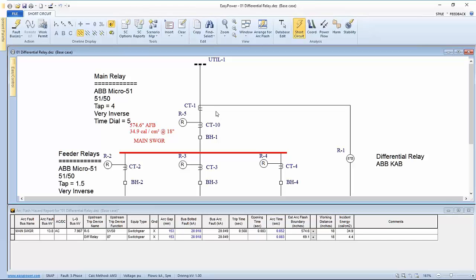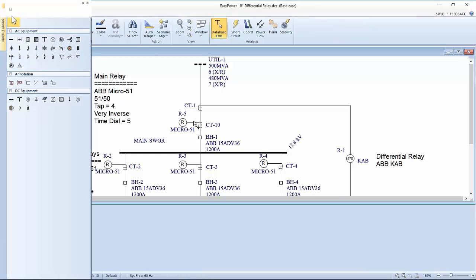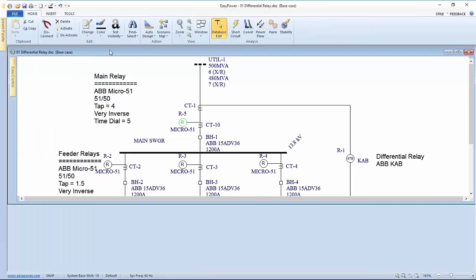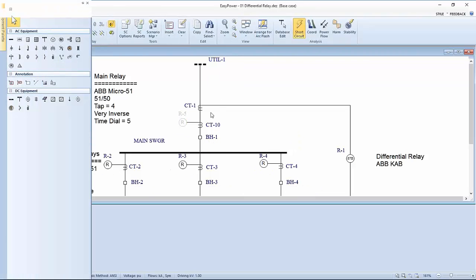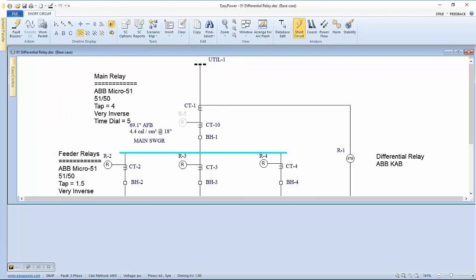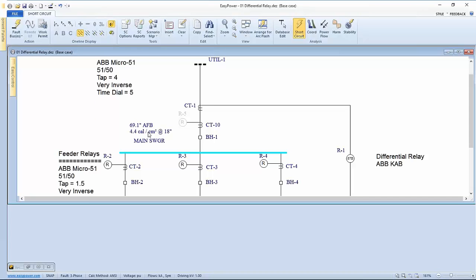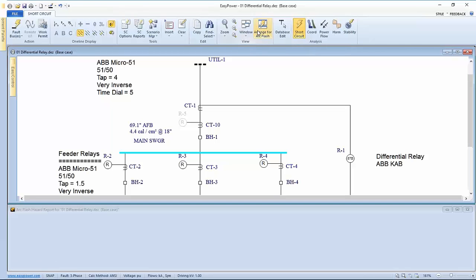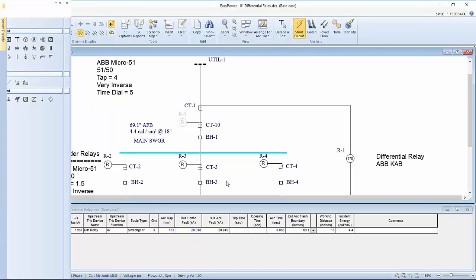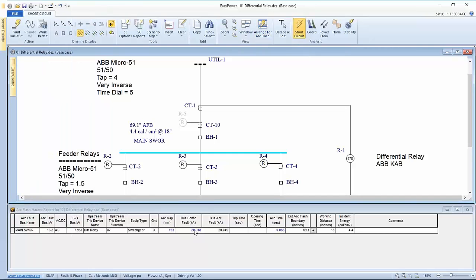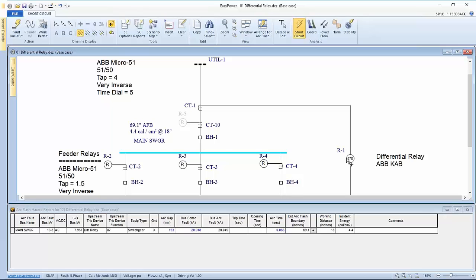The way we demonstrate that is, we go back and isolate, and go back to database edit. I'm going to deactivate this particular relay. Go back to short circuit, fault this bus, and now we can see our 4-calorie energy here. So the question becomes, what do we label this device? Clearly, because somebody may be working in the area and needs to know the full extent of the hazard involved, so the suggestion would be to put the total incident energy level on the label.